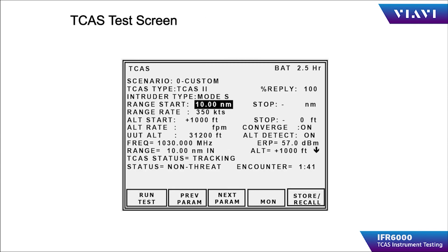Once the TCAS scenario is set up, the TCAS in the aircraft is configured to operate as it normally would in flight. These setups would include satisfying weight on wheels, air-ground switch in the airborne condition, landing gear in the retracted position, and radio altimeter. The operator then presses the run test soft key to initiate the scenario.